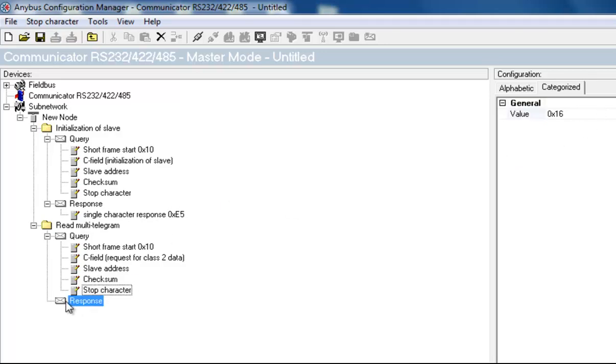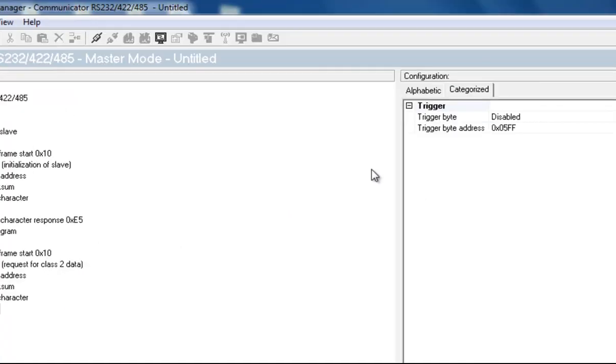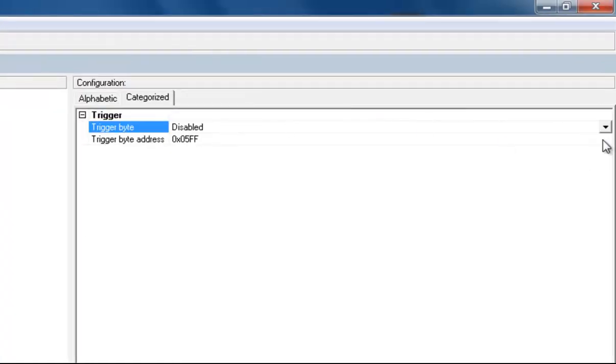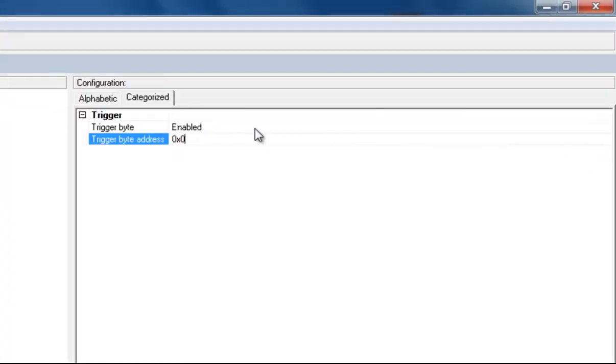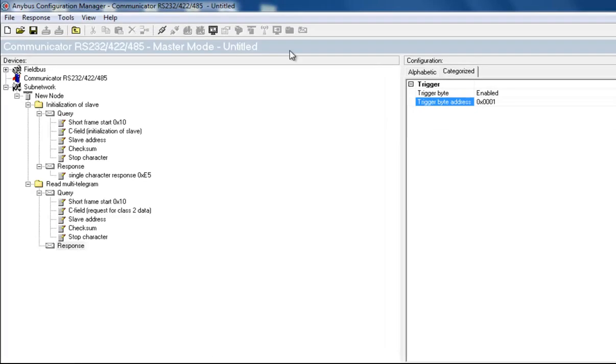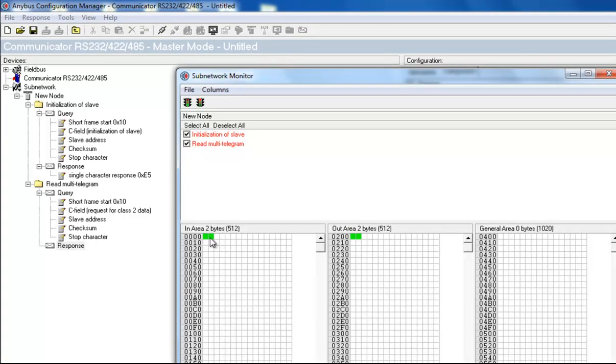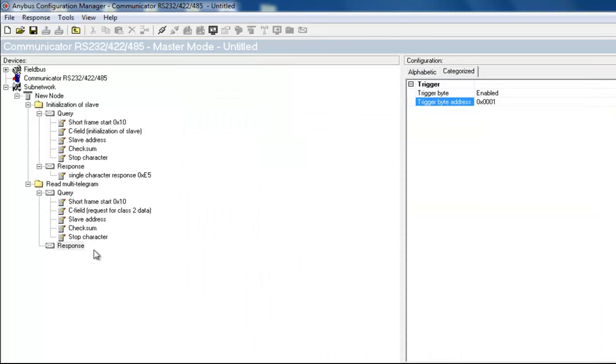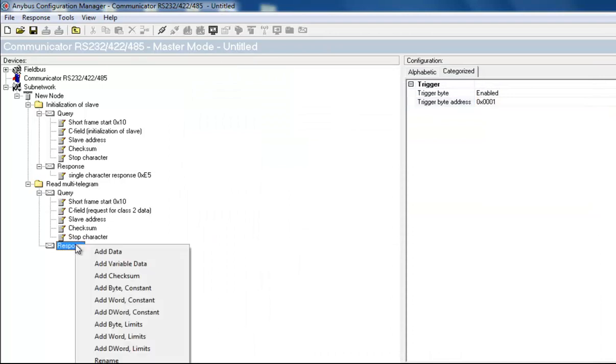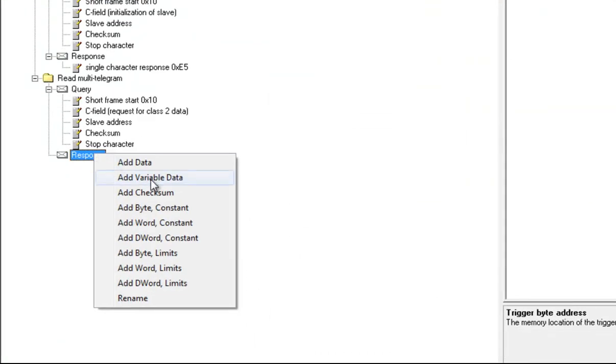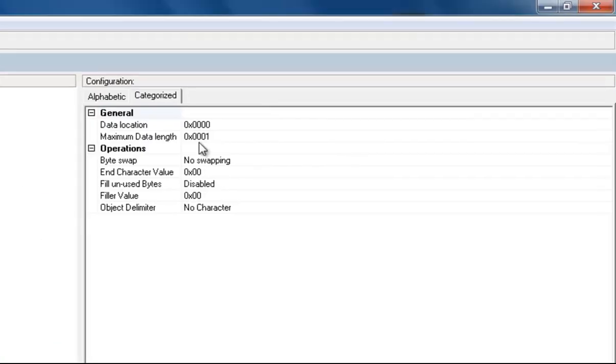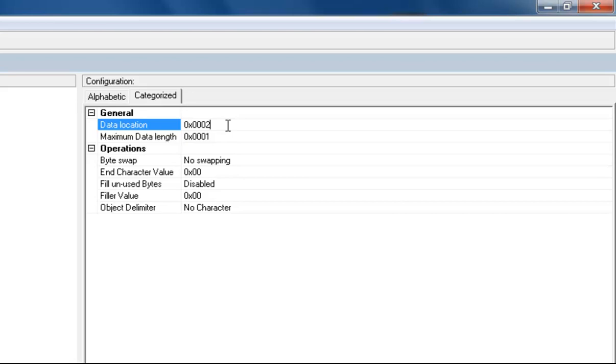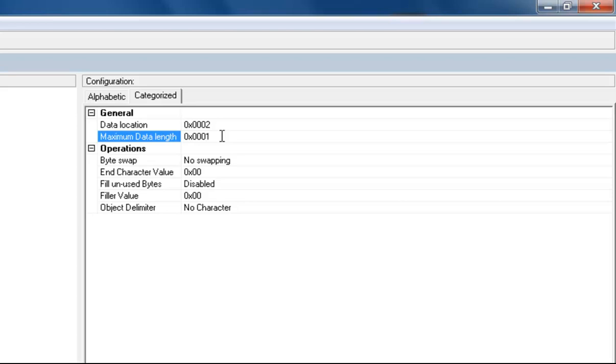The last thing I need to do is to configure the response from the energy meter. I enable a trigger byte and set this to address 1. I can see this in the subnetwork monitor. I add a variable data object, which I put on data location 2. This is the multi-telegram response of class 2 data from the energy meter, which will be routed to the Profibus network. I know that the maximum data size of the response will be 112 bytes long, 70 if we count hexadecimal. I therefore set the data length to 70.